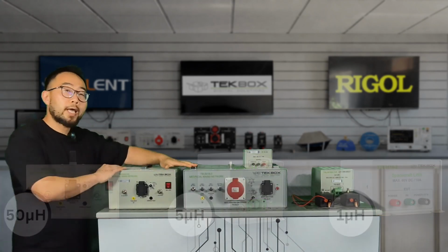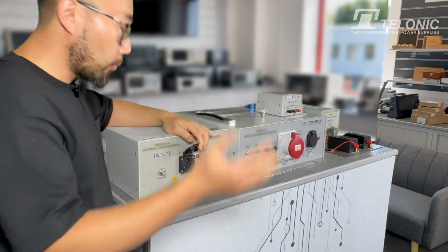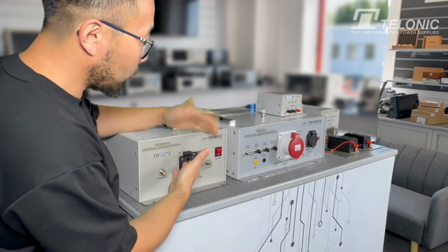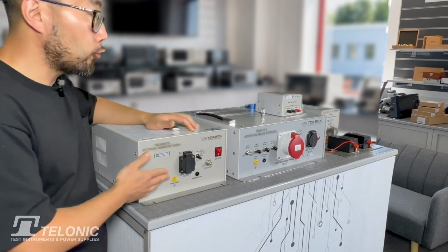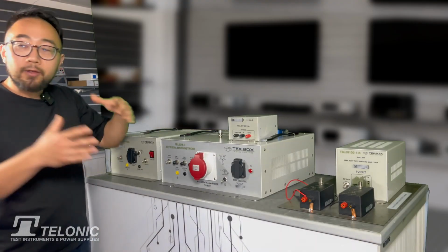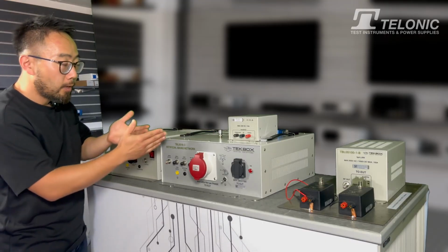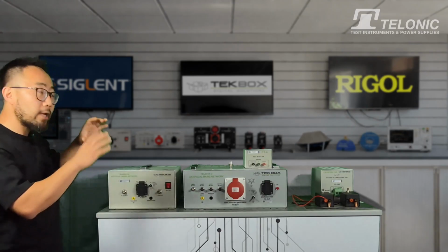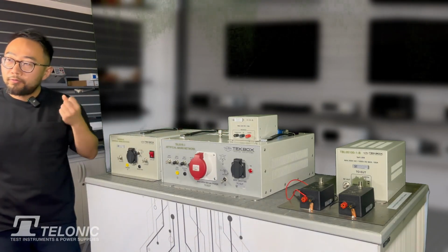Okay, so we first have a look at the AC types of LISN. This is a single-phase LISN, pretty straightforward. You plug a single-phase powered apparatus, such as a home appliance, into the EUT mains port, and then you measure the conducting emission either on the live line or neutral line. Similarly, you can plug three-phase equipment into a three-phase LISN and measure the conducting emission on L1, L2, L3 or neutral. We call these types of LISNs 50 microhenry simply because there is a big inductor inside this LISN, and it is 50 microhenry.